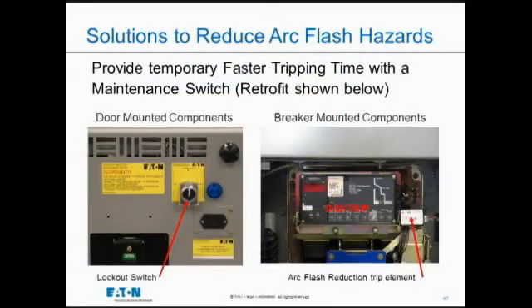So in the Eaton solution for maintenance switch, and we call that ARMS, Arc Flash Reduction Maintenance Switch, we reverted back to an analog tripping device to get the fastest response we could and put that onto a microprocessor device.